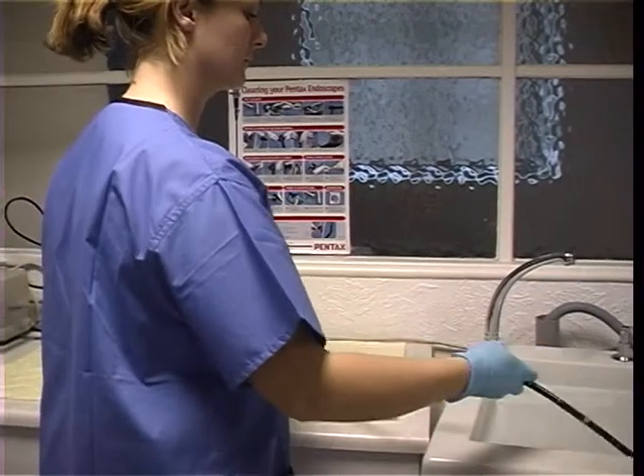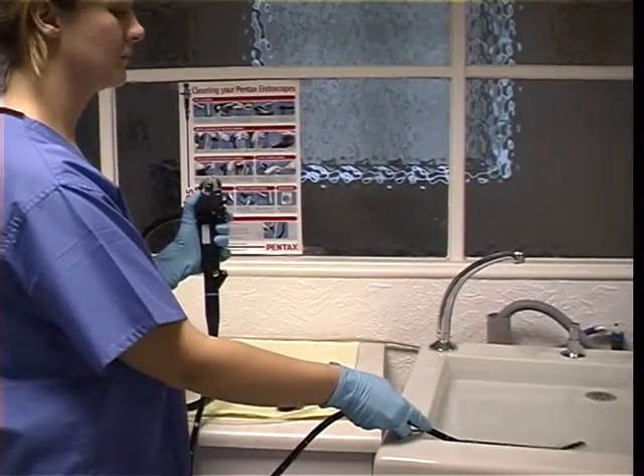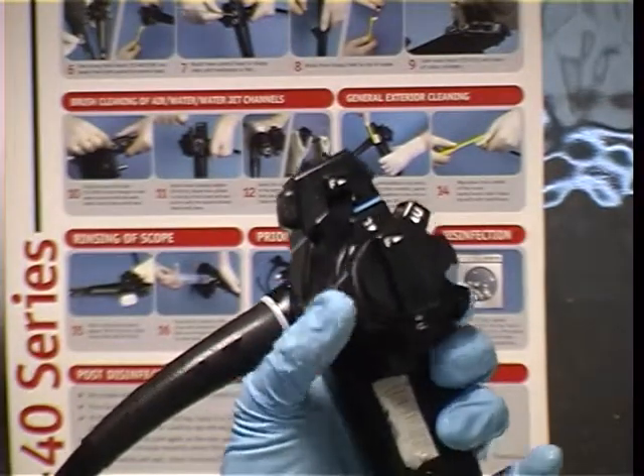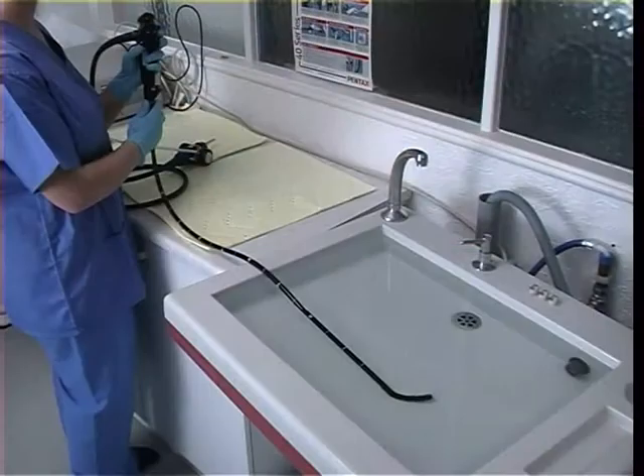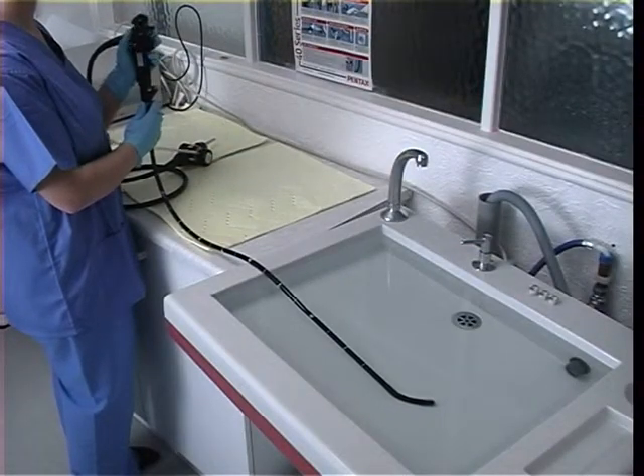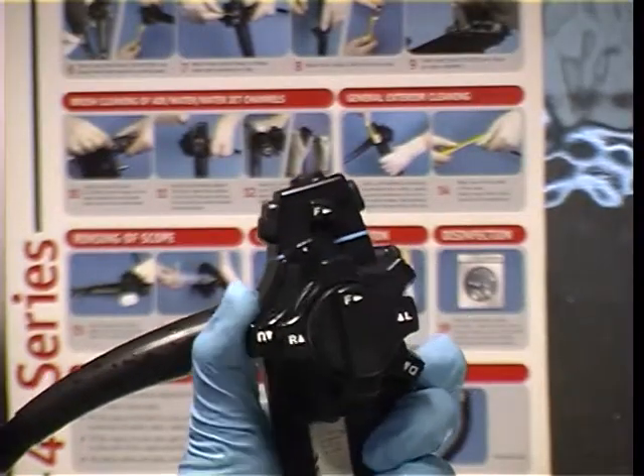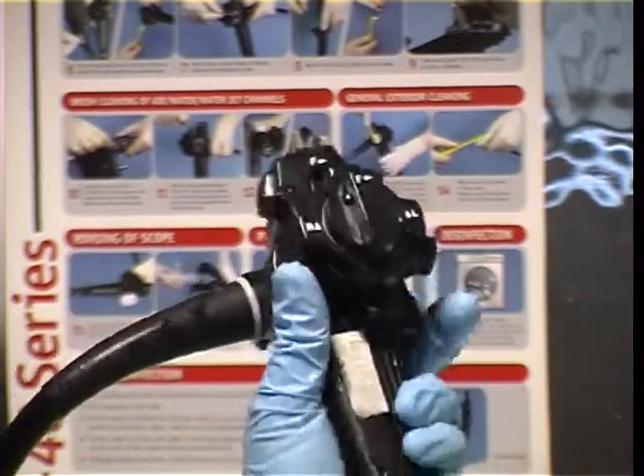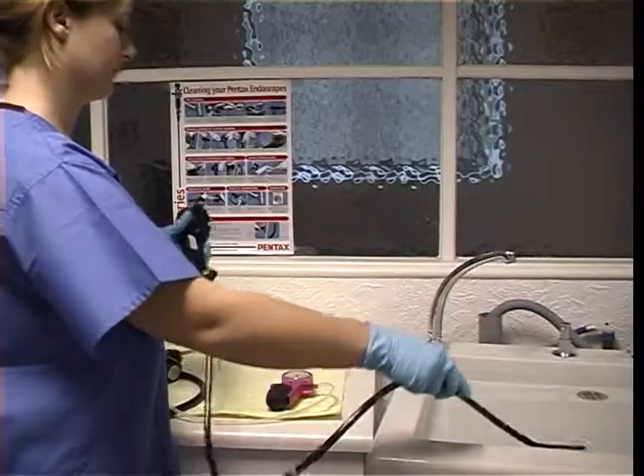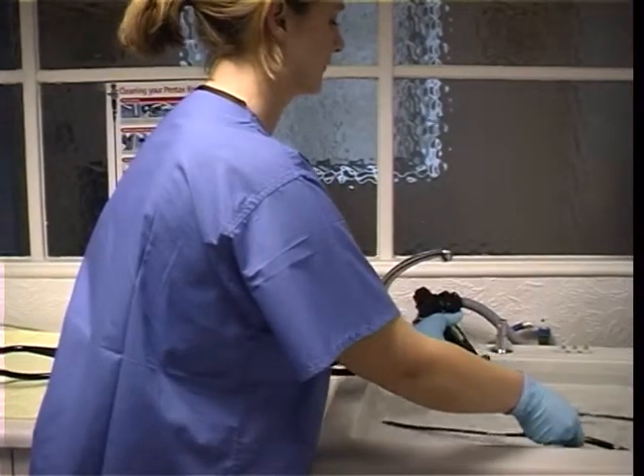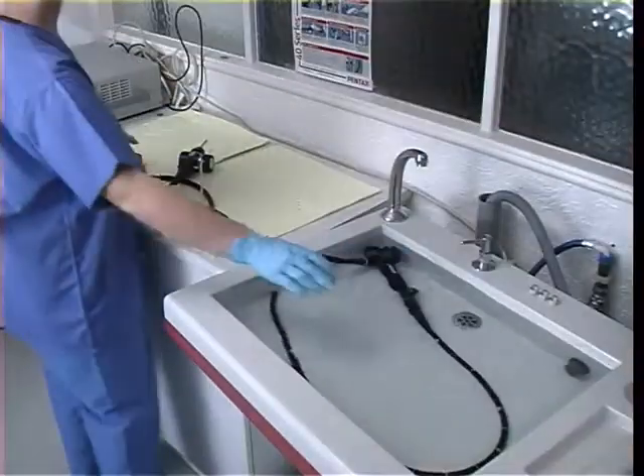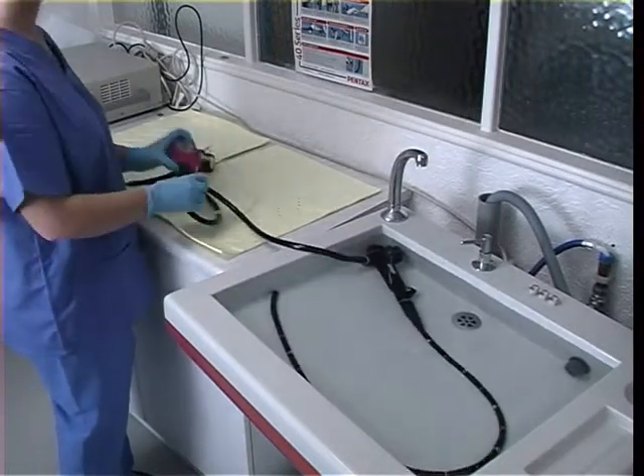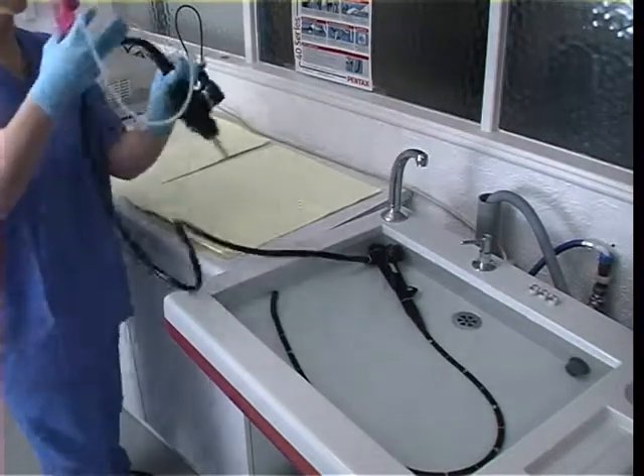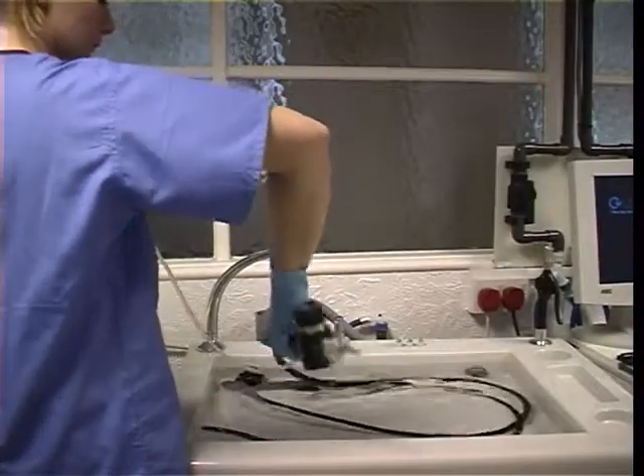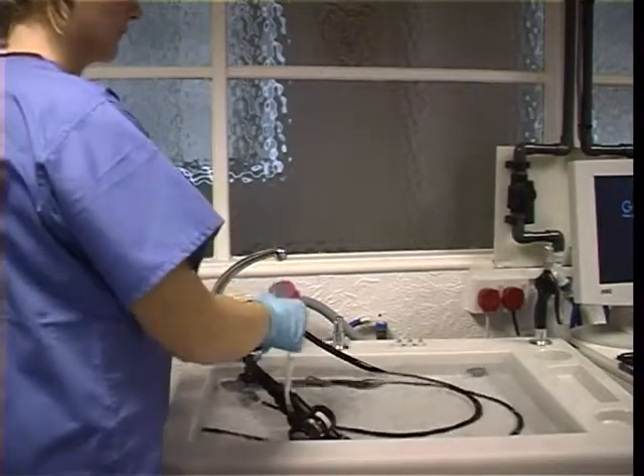If no loss of pressure is observed, immerse the distal tip in water and observe for any stream of bubbles appearing. If this does happen, then remove the endoscope, dry it and prepare to send it for repair. Do check the operation of the control head at this time by continuing on to angulate the distal tip fully in all directions, observing for at least 10 seconds between each angulation for any air bubbles. Immerse the entire insertion tube, control head, umbilicus and light guide post. You should then gently move the endoscope under the water to dislodge any surface air and again observe for any air bubbles rising. The complete leak test, immersion and observation procedure should take 2 to 3 minutes. You must be very careful not to immerse the leak tester.